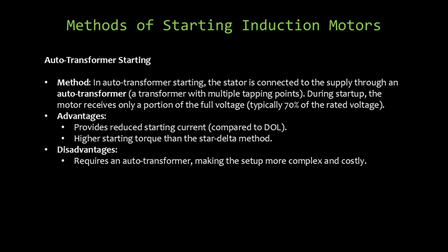The auto-transformer starting method offers another approach to motor startup. In this technique, the stator connects to the supply through an auto-transformer with multiple tapping points. During startup, the motor receives only a portion of the full voltage, typically around 70% of the rated voltage. This method provides reduced starting current and offers higher starting torque compared to the star-delta method.